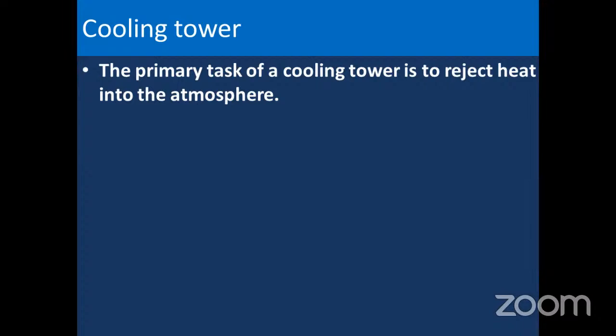Basically, the condenser outlet temperature will be less than 48 degrees. Am I right, sir? The steam exhaust temperature will be less than 50 degrees. The cooling water inlet temperature is at ambient temperature, and it can take away heat with a rise of temperature of at the most 10 degrees centigrade. So all this data is known to you already, right? So it can only rise 10 degrees above ambient, correct? No, it is not so. But the available temperature is very low.